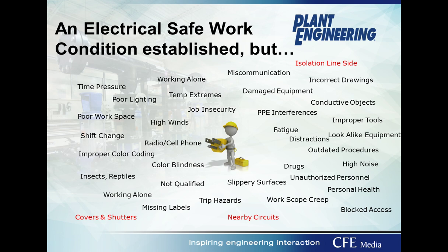The other term, in the lower left, is covers and shutters—covers on electrical equipment like switch gear, or shutters, commonly used in draw-out circuit breakers, low and medium voltage. There may be hazardous energy behind covers and shutters, so we need to be aware that we can't take off covers or open shutters that could expose workers to electrical hazards. If you open the door, remove a cover, or lift a shutter, you're immediately in very close proximity to hazardous electrical energy.